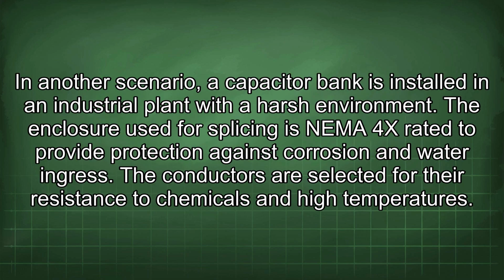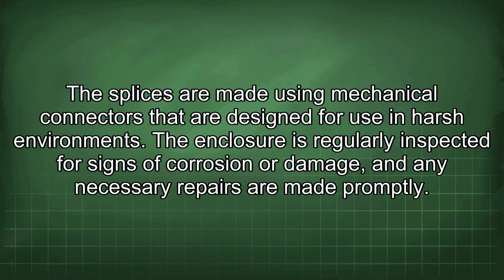In another scenario, a capacitor bank is installed in an industrial plant with a harsh environment. The enclosure used for splicing is NEMA 4X rated to provide protection against corrosion and water ingress. The conductors are selected for their resistance to chemicals and high temperatures. The splices are made using mechanical connectors that are designed for use in harsh environments. The enclosure is regularly inspected for signs of corrosion or damage, and any necessary repairs are made promptly.